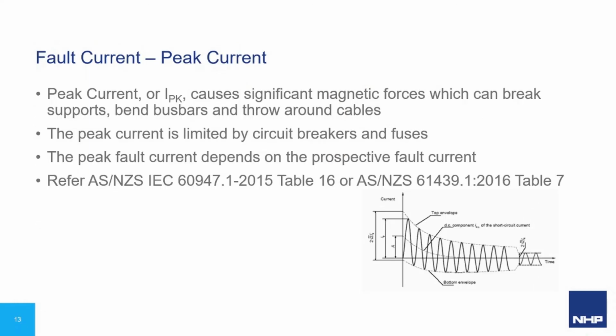The second value we arrive at is the peak current, or I peak. The peak current of the prospective fault represents the highest instantaneous value that could occur during the fault as opposed to the RMS fault. The peak current causes significant magnetic forces which can break supports, bend bus bars, and throw around cables. From testing, we can assign our equipment a peak rating which we should not exceed. The following video shows what happens if the peak current rating of the chassis is exceeded during a short circuit fault.